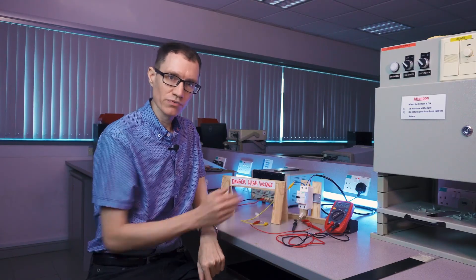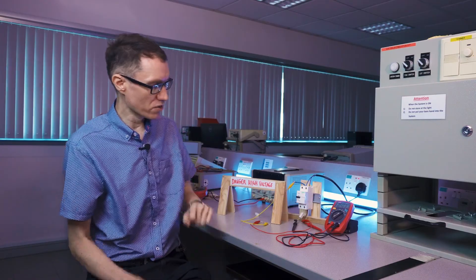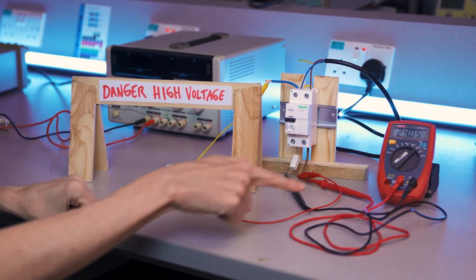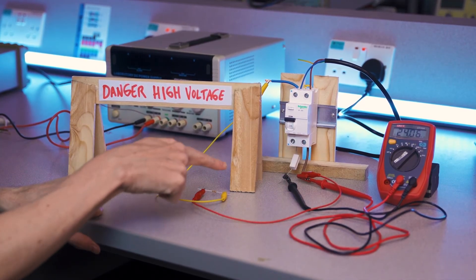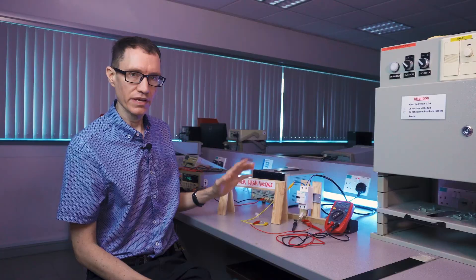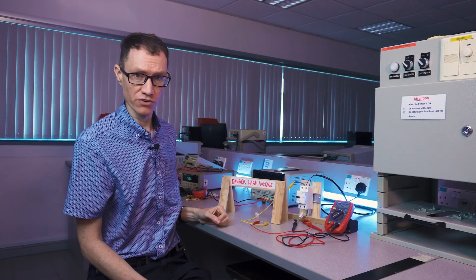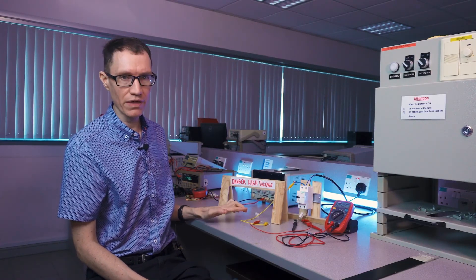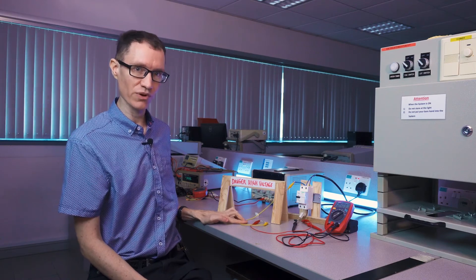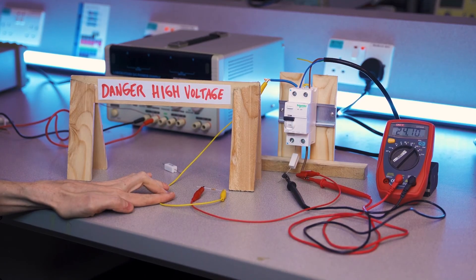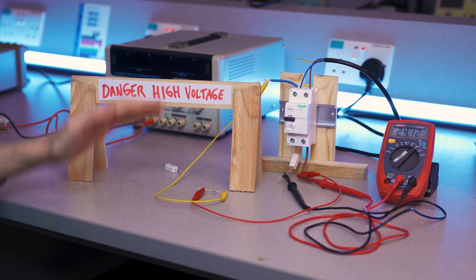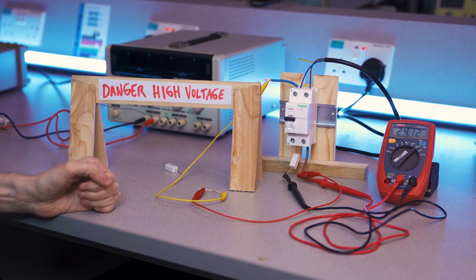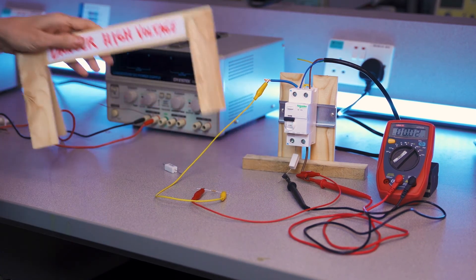We still have around 23 milliamps flowing through our load, but we also have 5 milliamps flowing through this fault condition. It's not enough to cause the circuit breaker to trip, but if I were to lower down this resistance such that the current flowing through the fault is more than 10 milliamps, then it should cause this circuit breaker to trip. We're going to do that next.